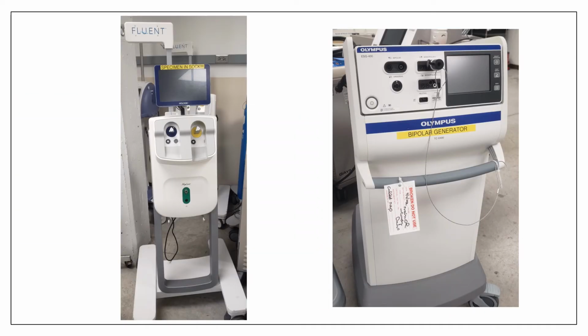These are two pieces of equipment right here. On our left, we have our Fluent or MyoSure machine, which provides liquid distension of the uterus. So they use this for diagnostic and operative procedures. It's called a hysteroscopy. So they're going in to look inside the uterus. And this machine can monitor a volume difference between irrigation fluids, which is very important. You want to monitor how much fluid you're putting in and how much fluid you're getting out. And this machine will monitor all that for you.